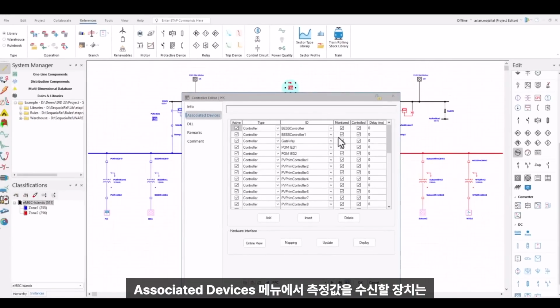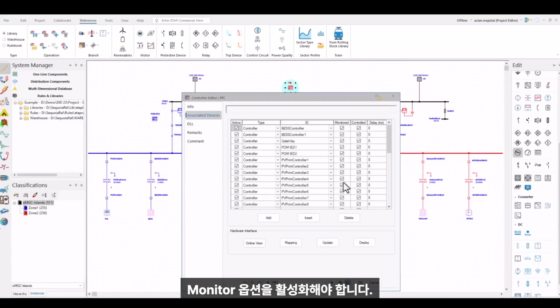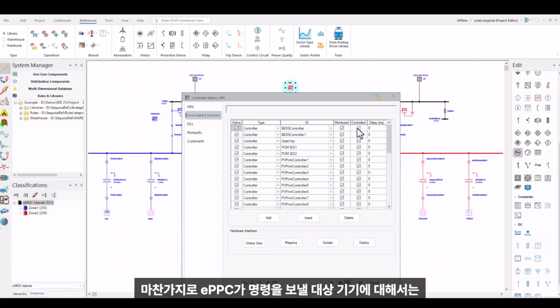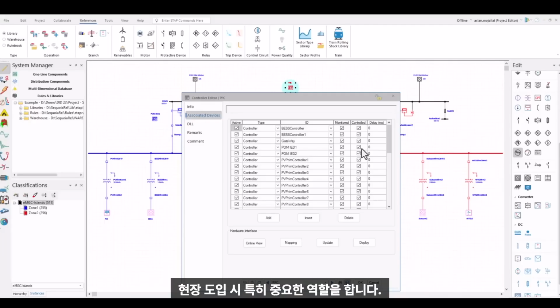Within the Associated Devices page, we should enable the monitor option for any device from which the ePPC needs to read the measurements. Similarly, we should enable the control checkbox for any device that ePPC is expected to send commands to. These settings are especially important for hardware-in-the-loop or HIL testing, as well as for field deployment, because enabling or disabling these checkboxes affects the input and output and DNP3 tag assignment.